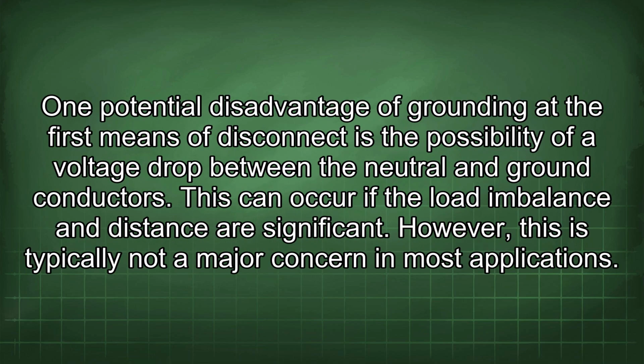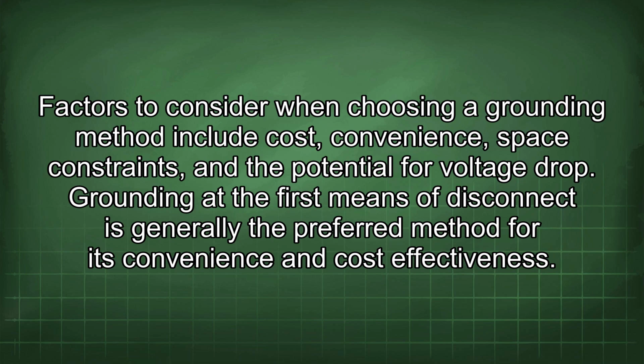One potential disadvantage of grounding at the first means of disconnect is the possibility of a voltage drop between the neutral and ground conductors. This can occur if the load imbalance and distance are significant. However, this is typically not a major concern in most applications. Factors to consider when choosing a grounding method include cost, convenience, space constraints, and the potential for voltage drop. Grounding at the first means of disconnect is generally the preferred method for its convenience and cost effectiveness.